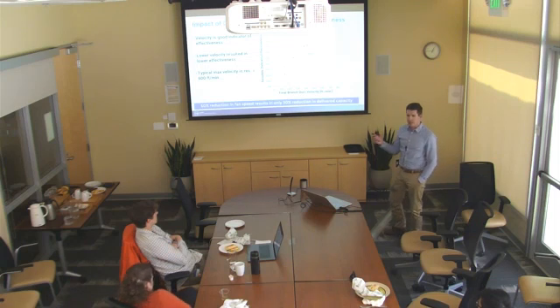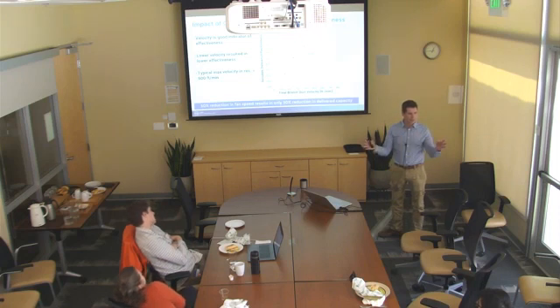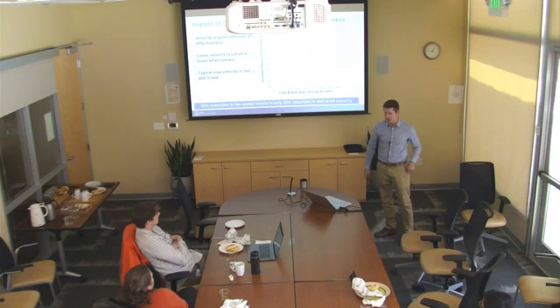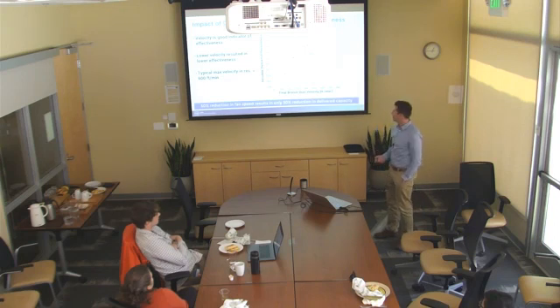So what we did was look at velocity, and it seems that velocity is a good indicator of that performance. Velocity in a duct system changes all the time because there are branches, so what we're looking at is the final branch velocity. This is the velocity just before it reaches the grill, so the final duct run. Say you have an 8-inch, just the final velocity there. What you can see is there's a really strong correlation between that final velocity and the performance, or the delivery effectiveness, of your duct. The really poor performing ducts had really low velocities at the end of the branch versus the better performing ones up here.